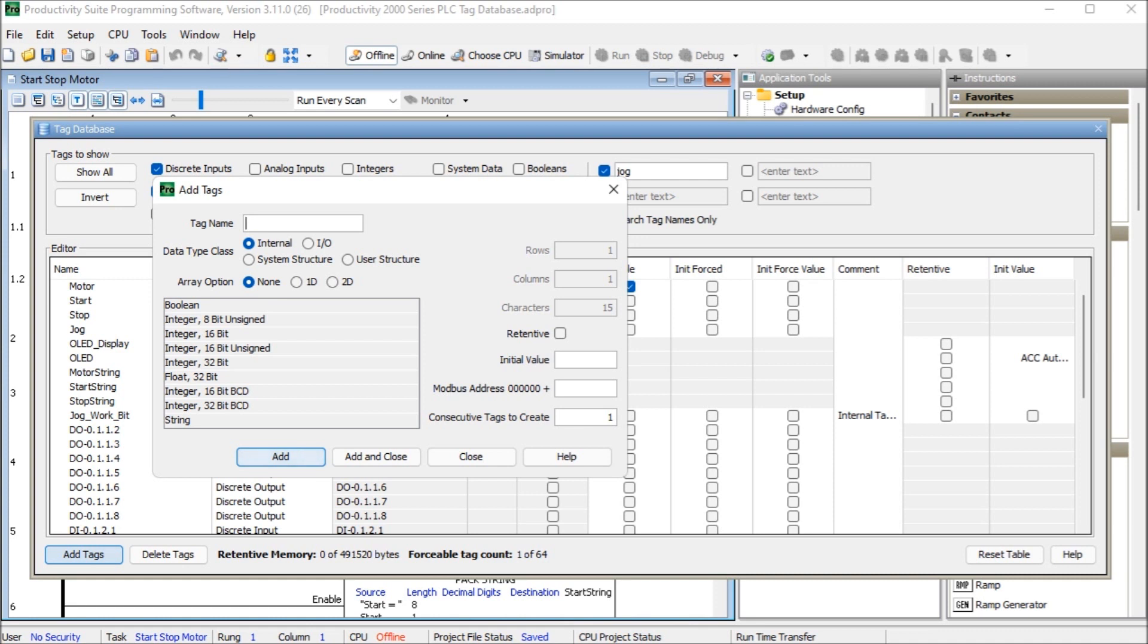Then we have the integer 16-bit BCD. And so this is an unsigned binary coded decimal or BCD. And we'll have the range from 0 to 9,999. These are used for tags that only be represented by the decimal numbering system, 0 to 9 for each digit.